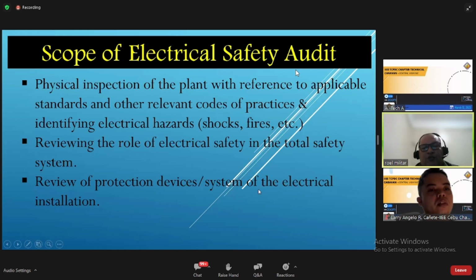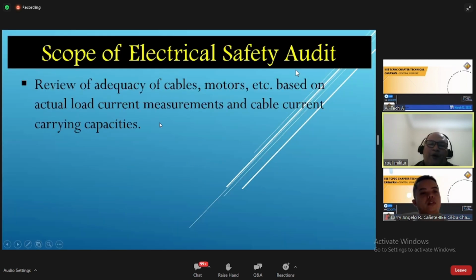It will review also the protection devices and systems of electrical installations, and the adequacy of cables, motors, etc. based on actual load currents, measurements, and cable current carrying capacity. So this will most likely be applicable, especially if the buildings have been operating for many years after the installation, no? Let's say 10 to 15 years. Every time there is occupancy, or they start to operate, most likely a lot of additional loads will come in. Okay, so there must also be a review of the adequacy of the cables, motors, and cable carrying capacities if still suitable for the operations.